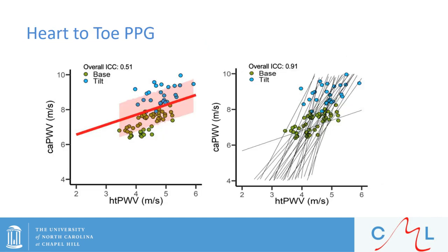These are findings from a paper currently under review, in which we looked at photoplethysmography pulse wave velocity. Specifically, we looked at agreement between heart-toe pulse wave velocity via PPG against standard carotid-ankle pulse wave velocity via the Vicorder oscillometric system. We found moderate overall agreement between these two devices. We also looked at repeated measures agreement following an orthostatic challenge and found strong agreement.